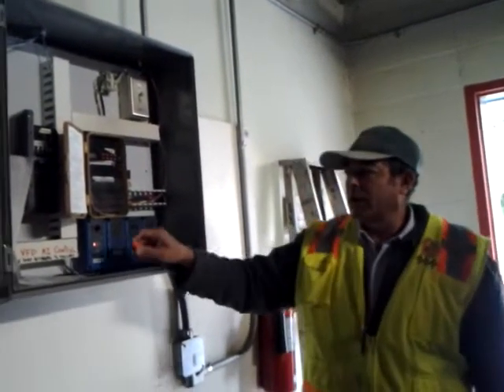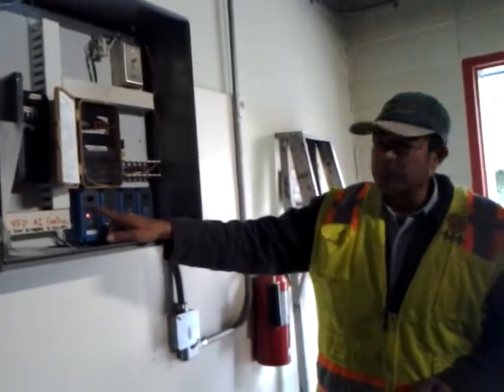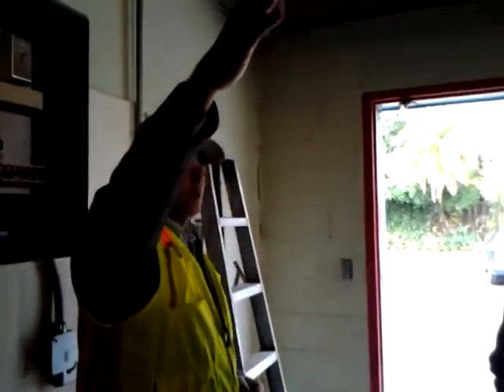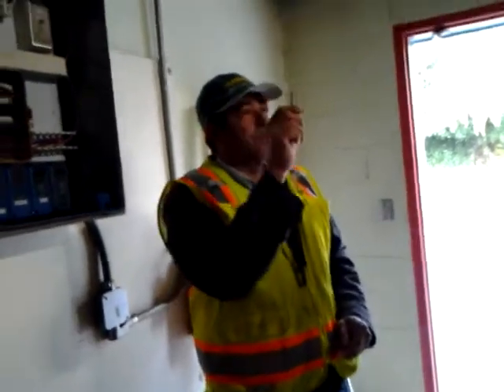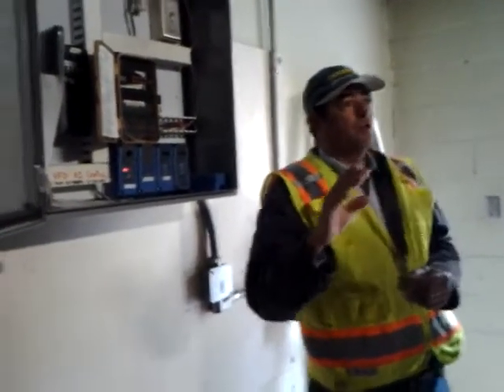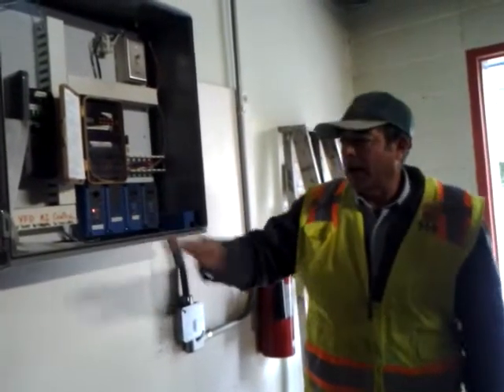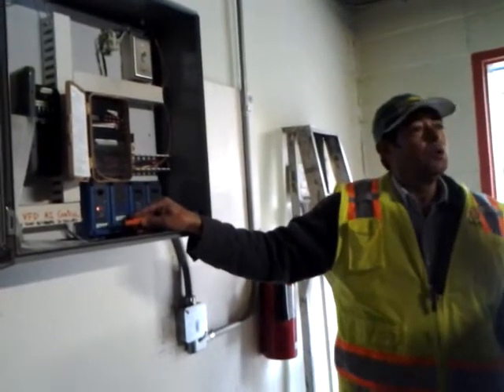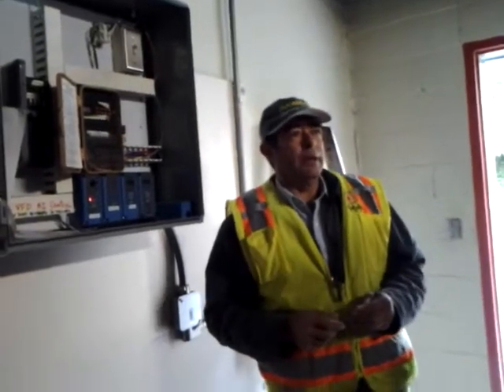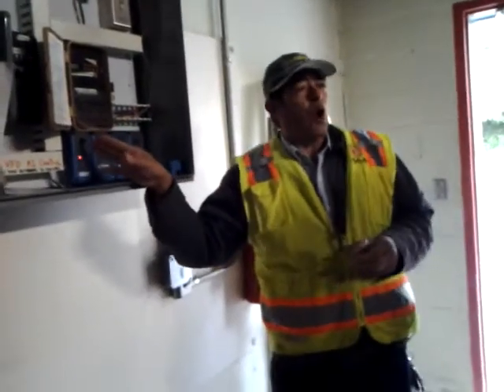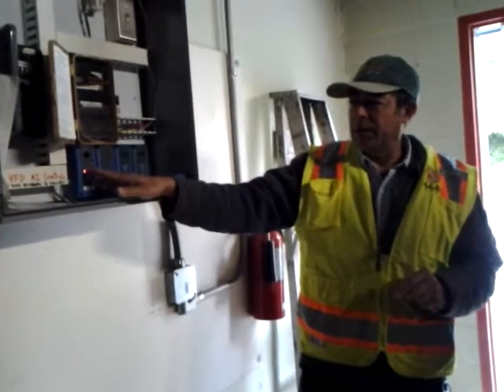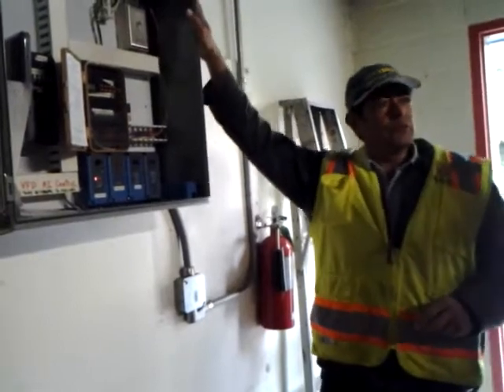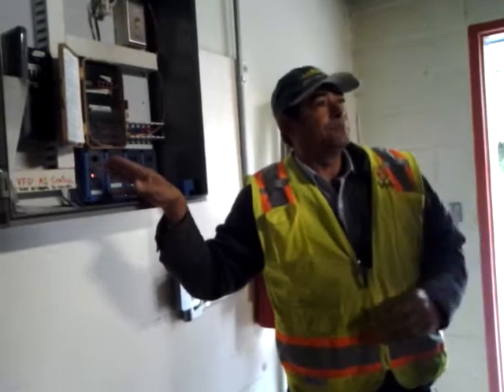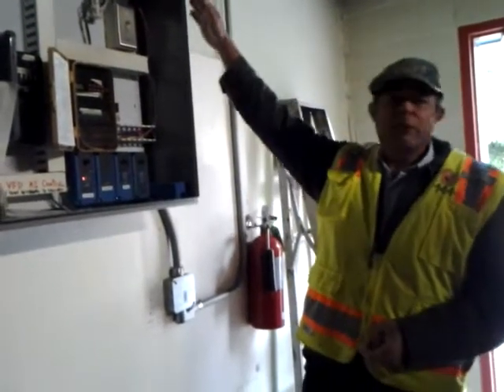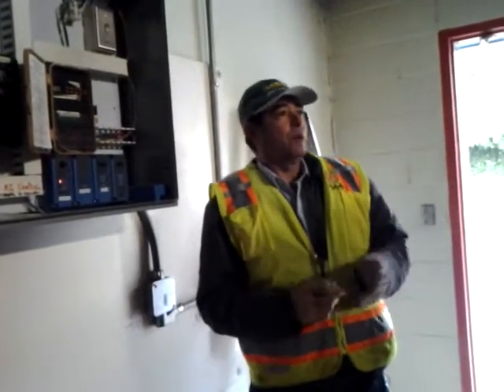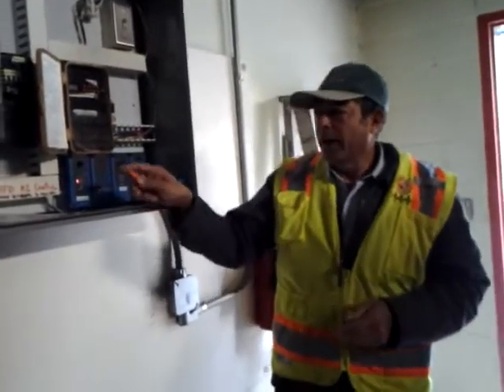Now, the way it really works is this little thing sends, let's say, 10 volts or 24 volts of electricity to that sensor. And it is fairly simple. It has a resistor in it. And depending on how much resistance there is, that's how much electricity is going to come back to here. And it is set, if you notice, from 2 to 10 volts. 2 volts DC means that it is almost at temperature. So this will send an impulse again to the variable frequency drive. Now they're talking electronically. This is telling the variable frequency drive, hey, it is almost time to start working, and it starts very slowly. So that's what this does.